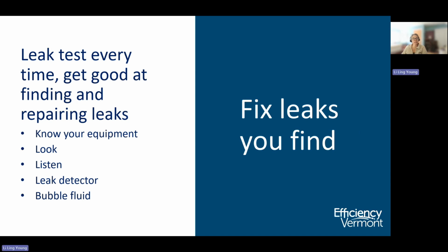Leak testing at installation is required before introducing refrigerant into the lines. Use leak detection fluid at the joints. It's also a good idea to check for leaks whenever you service a system for whatever reason. When you're doing your visual inspection, suspect a leak if you see oil residue. We'll return to this when we talk about tools, but you really need to know how to use your leak detector. Once you think you know where there's a leak, use leak detection fluid to pinpoint the exact location.